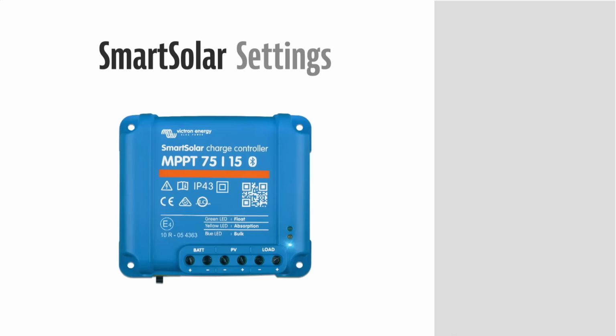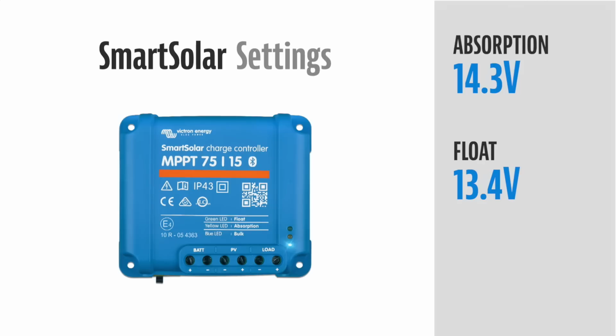So here's what we're going to do. We're going to go with generic 12 volt lead acid battery charging settings. Tap user defined for the battery preset, set the absorption to 14.3, the float to 13.4, and the equalization to 14.3. The rest of the settings we left as is.